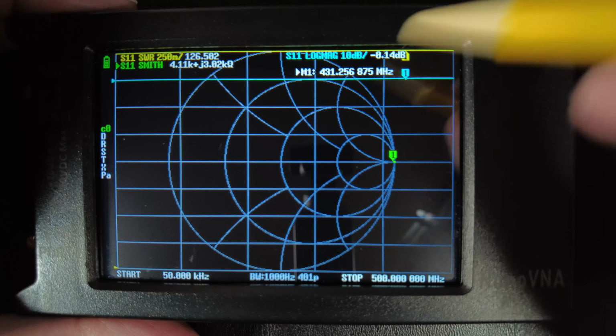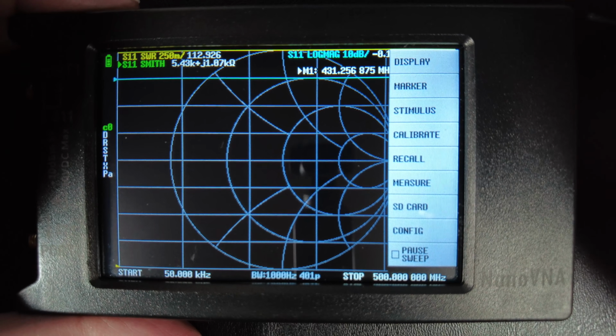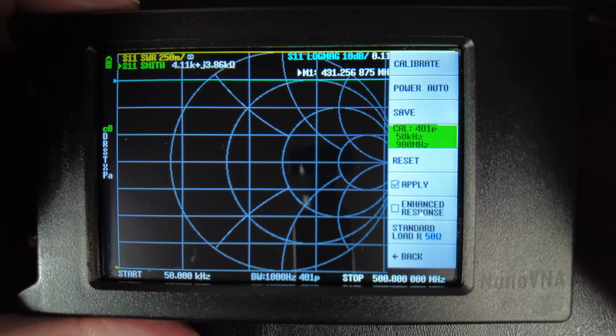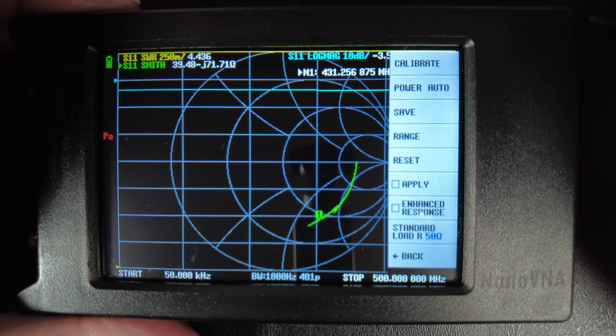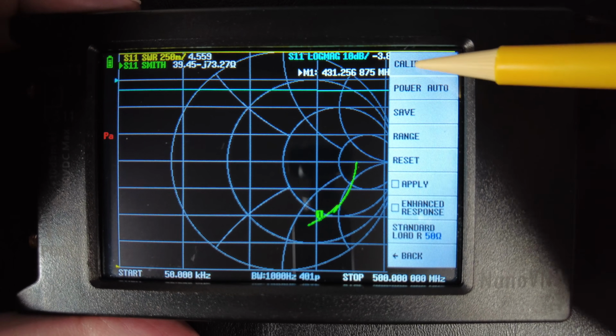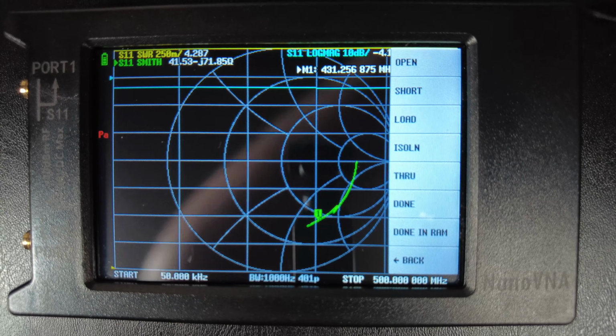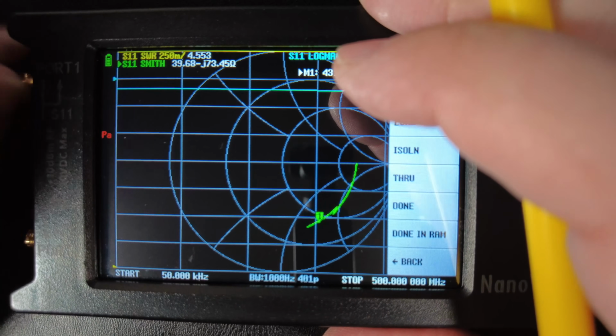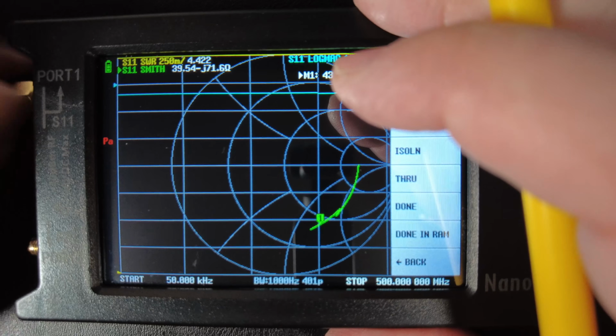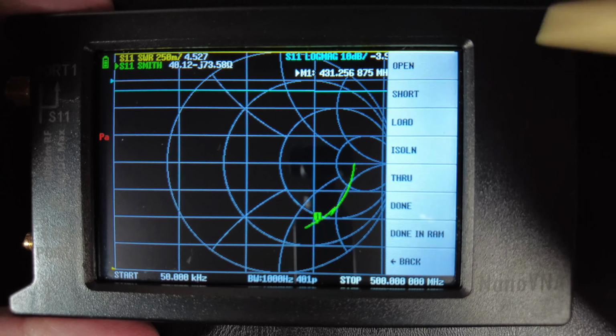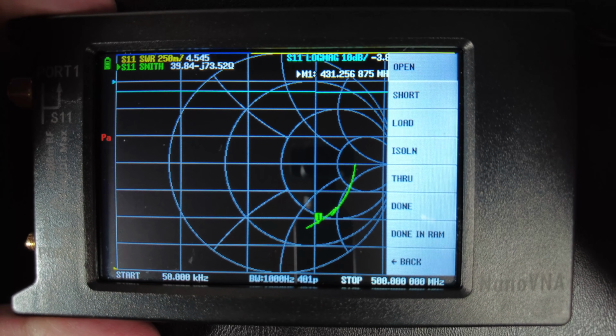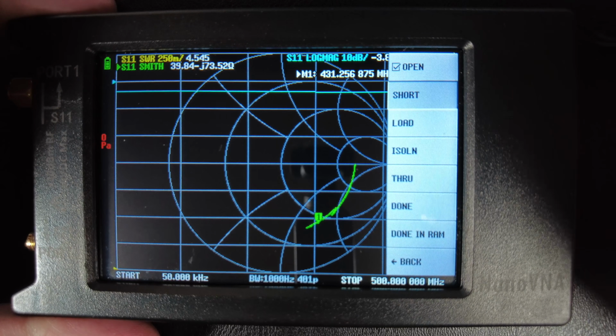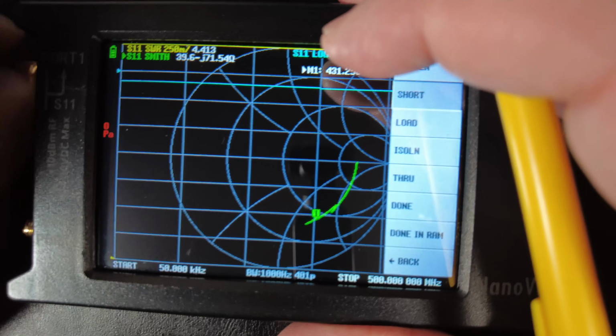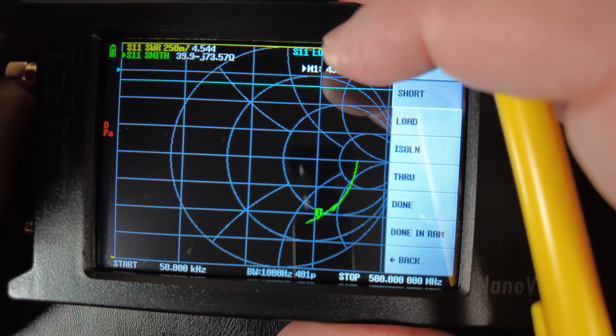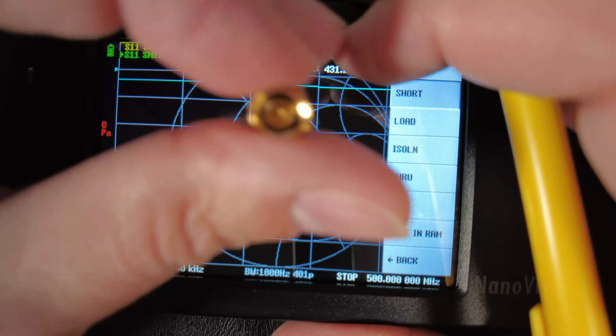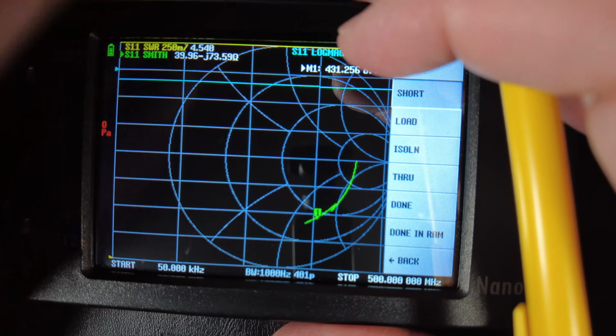All right, now to do the calibration, we want to go back to the main menu and hit Calibrate, and then reset to clear out what calibration is already set there. Then we'll hit Calibrate, and we'll start with the open. Okay, so now I'm screwing on the open part of the calibration kit. And we'll hit open, let that do its thing. Now we need the short. And by the way, you can tell the difference between the open and short because when you look inside the cap, you'll see it has no pin, and the short will have a pin.